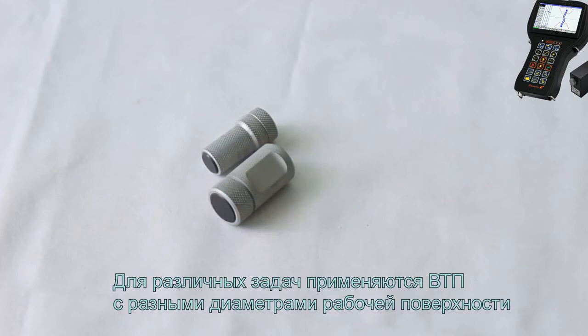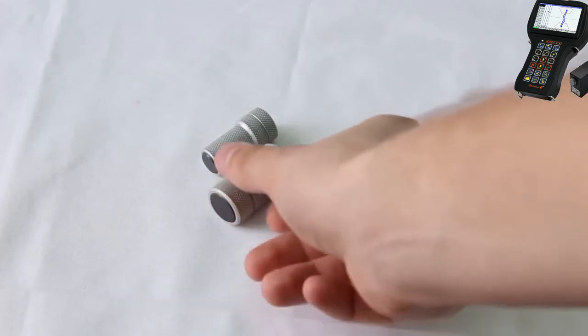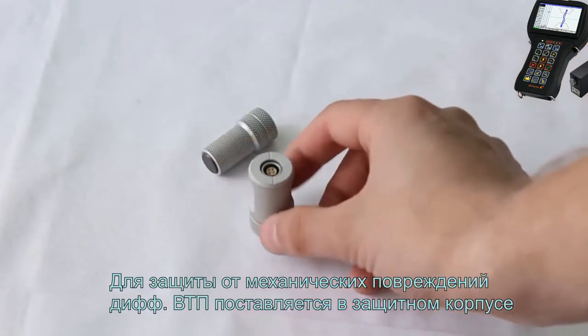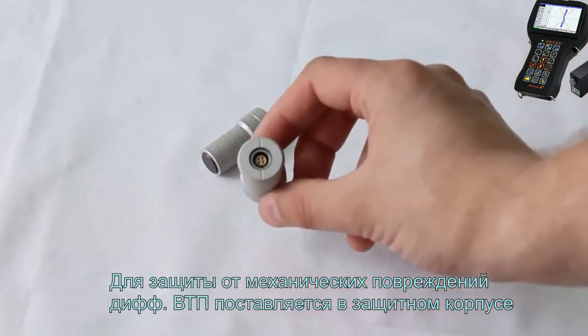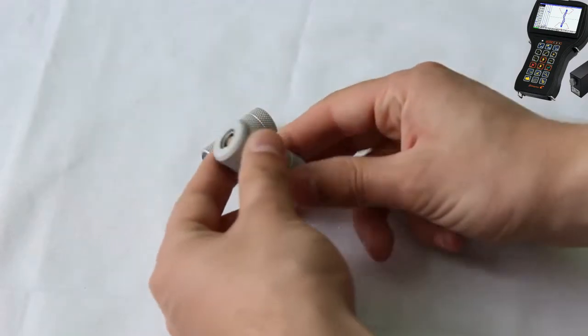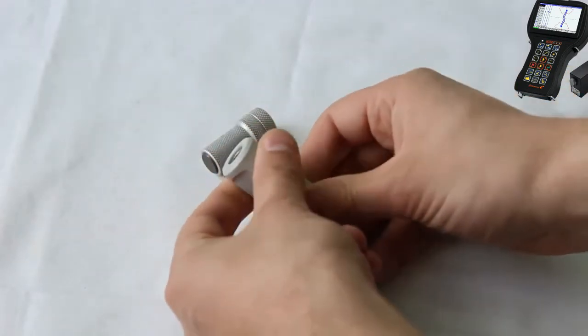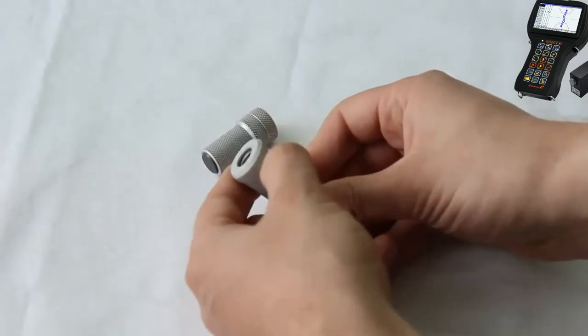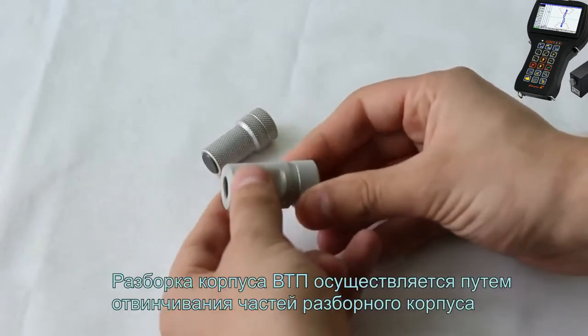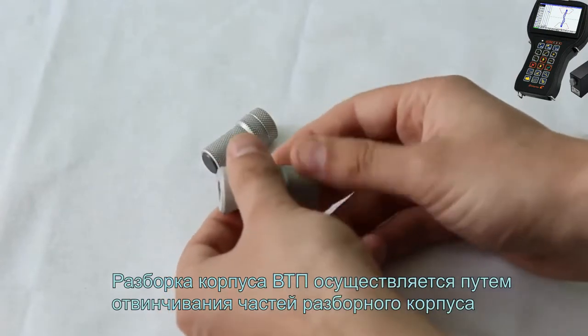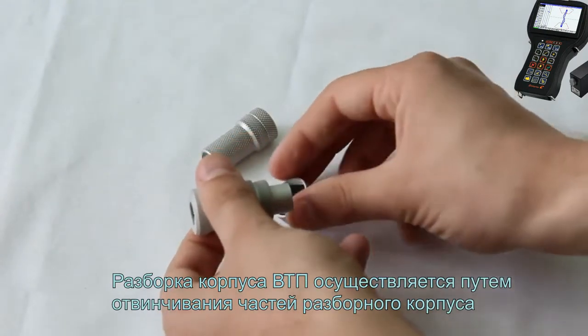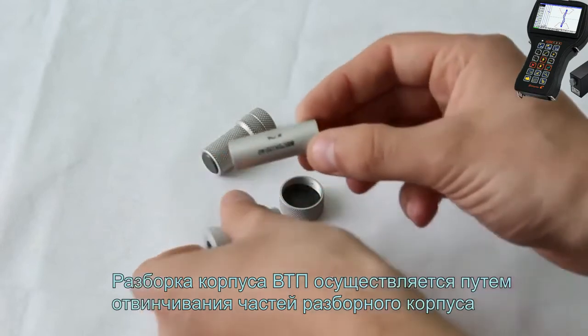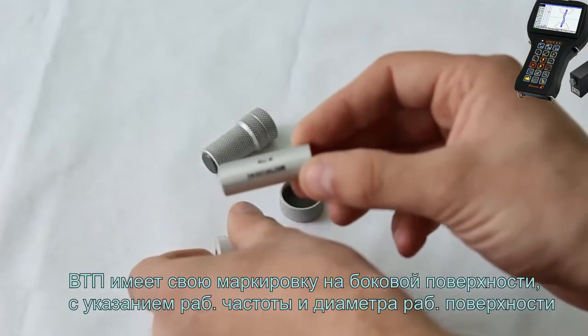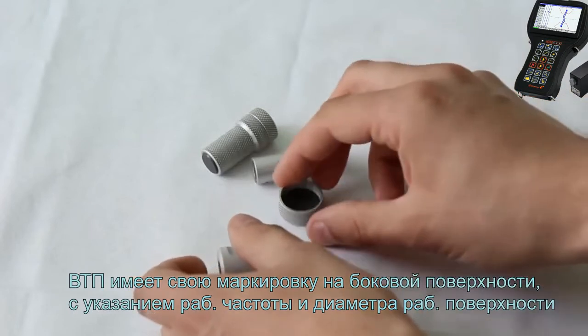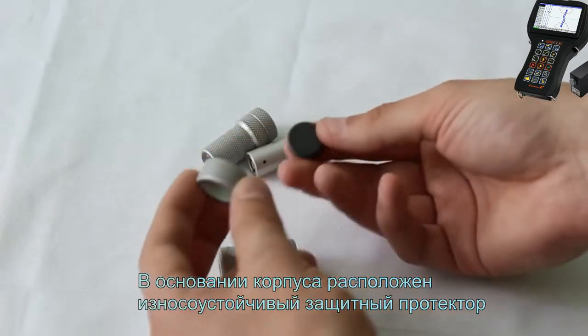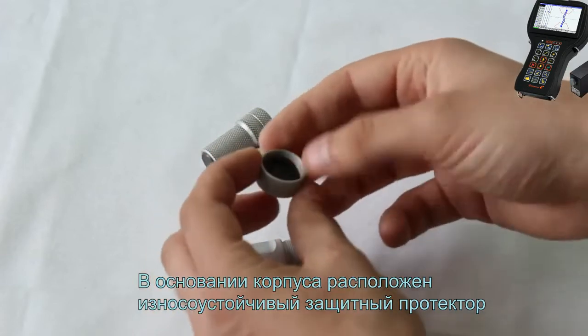Different tasks require the application of EC probes with different diameters of operating surface. Differential EC probes are delivered in protective housing to be protected from mechanical damage. The housing of the EC probe can be dismounted by unscrewing the dismountable parts of the housing. The EC probe has its designation on the side surface where the operating frequency and probe diameter are indicated. A wearproof protector is located on the bottom side of the housing.